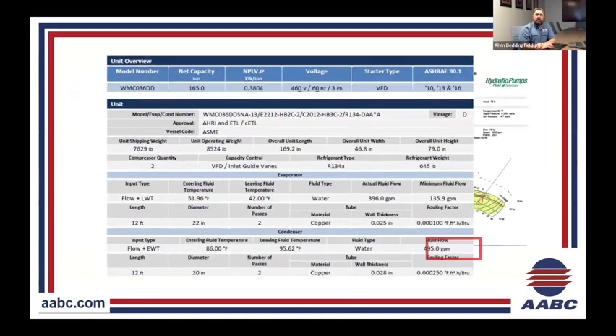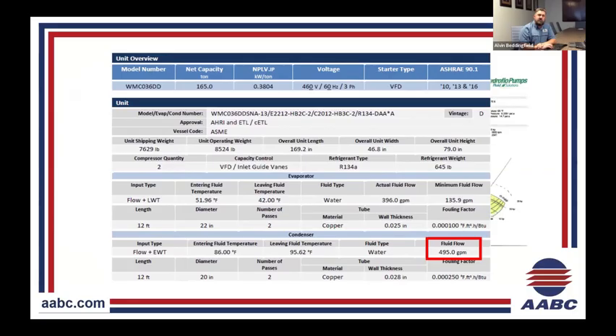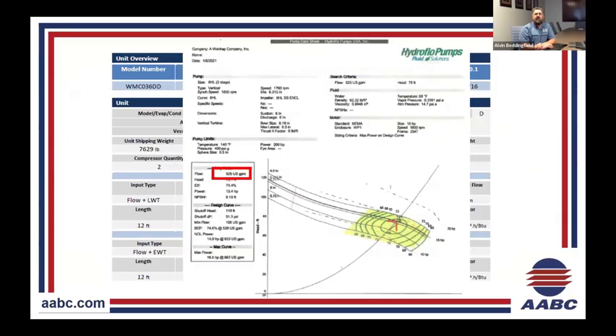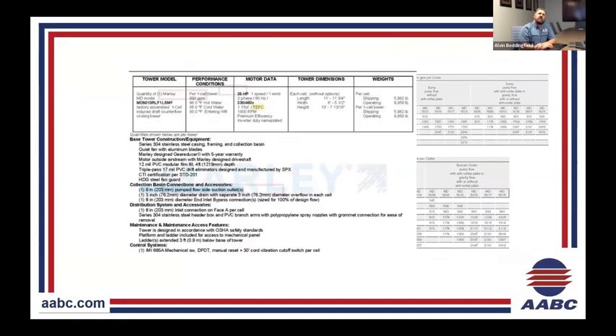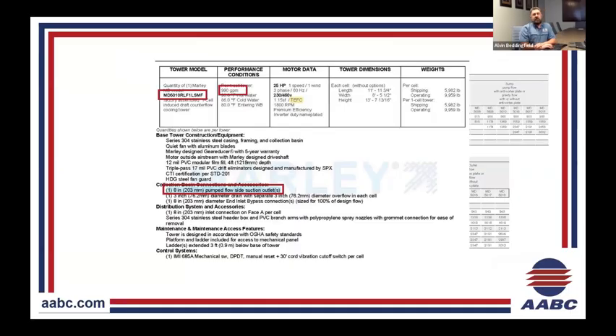So we're going to go through the chillers. We needed to make sure that where we designed, we weren't too high. Can the tower handle what the chillers can do, or do we have too much flow? Going through it, we took our measurements across the chillers when we were determining the low flow scenario, and we came across 495. I think we set them up for 510, 515. The pumps had a little bit of excess and extra curve on them, set at 525. We throttled them a little to get them closer to that chiller curve. So we set the system up around 510 on one chiller and 515 on the other. The cooling tower was designed at 990, so we knew we were right there on the flow.